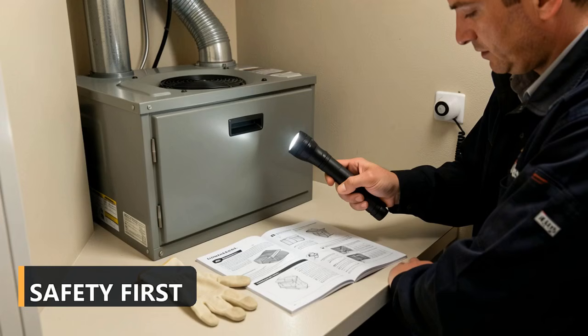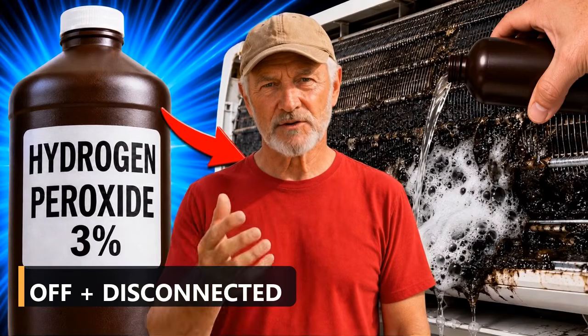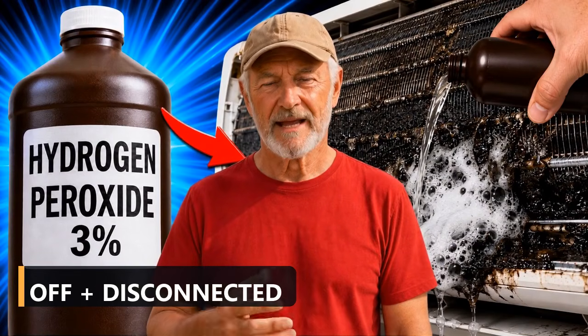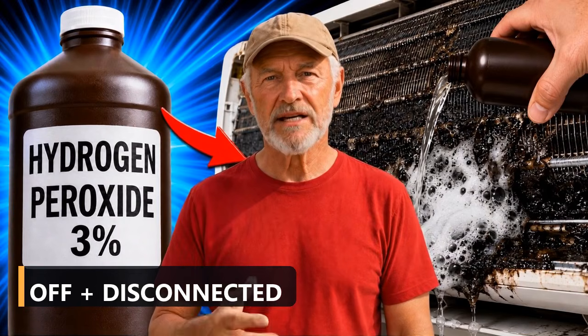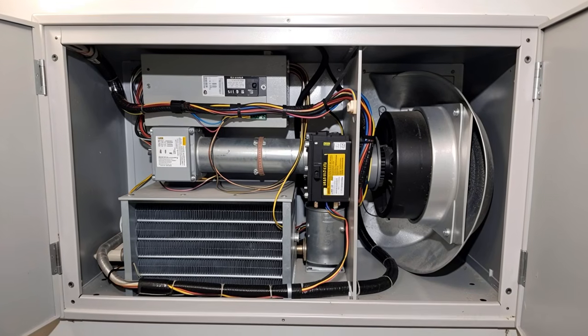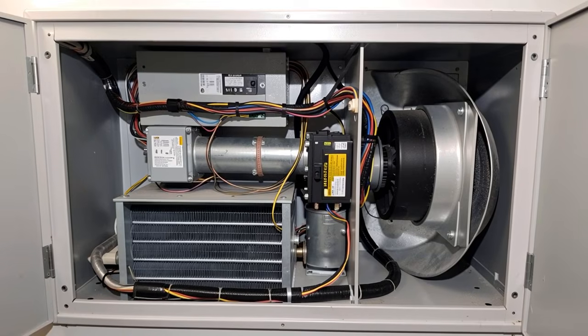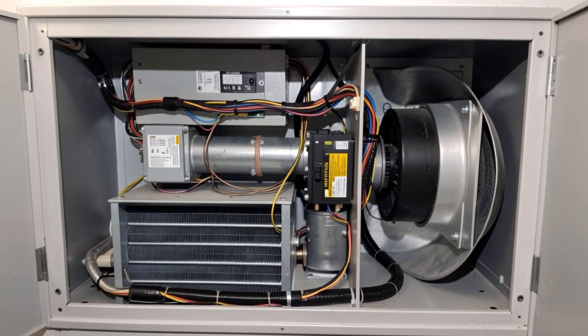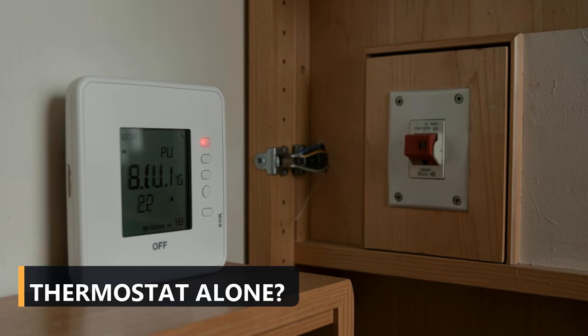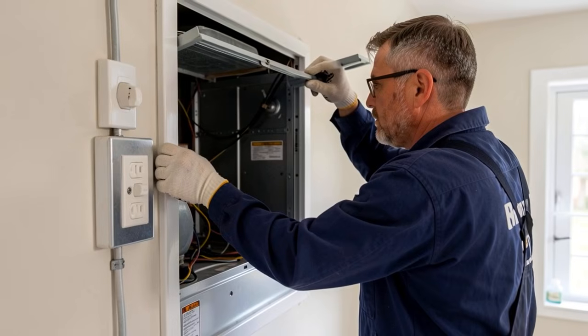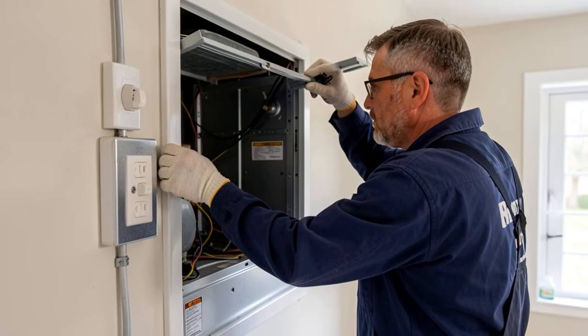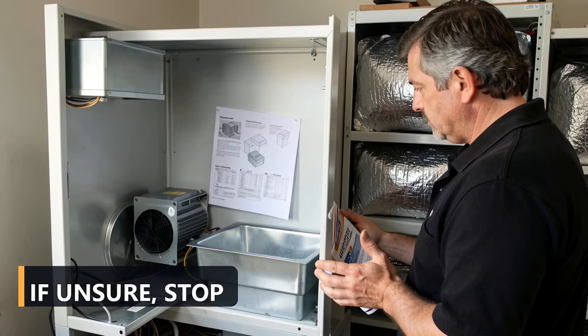Before anything touches the equipment, the system is switched off at the thermostat and at the electrical disconnect or breaker. An indoor air handler contains wiring, controls, motors, and components that should not be exposed to careless spraying. Turning the thermostat off alone may not isolate every energized part. Access panels should not be opened unless the power is safely disconnected and the manufacturer's instructions permit homeowner access. If you cannot identify the coil, drain pan, and electrical compartment with certainty, stop there.